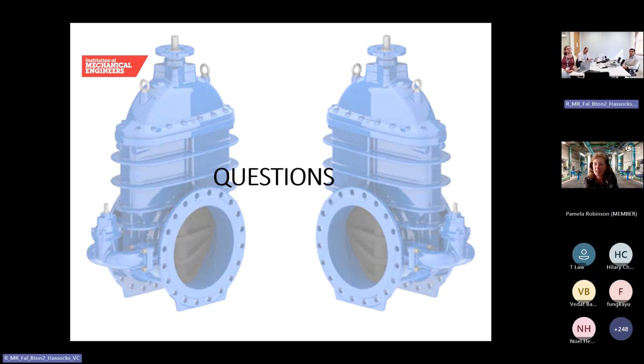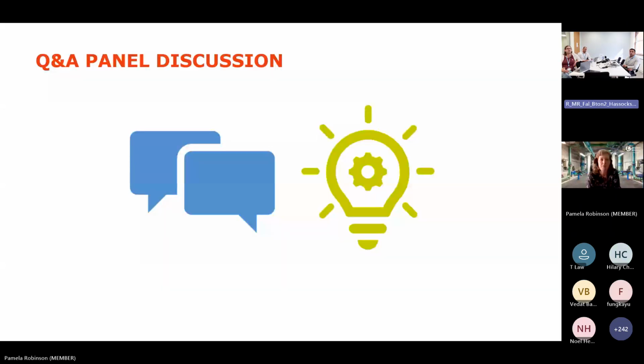So we use full bore and clear bore where, as was stated in the presentation, pipework is round, for example, but the throat of an eccentric plug valve can be rectangular. So if your pig is round, it's not going to go through a rectangular bore, even though the cross-sectional area is the same. Although it's not having an impact from a flow velocity perspective, you can't get a fairly stiff round pig through a rectangular hole. So that's why sometimes you have to specify clear bore, so that the throat of the valve is round and you can get a pig through it. Of course, if you're ice pigging, it doesn't matter, but with traditional pigging, where you've got big launchers and that in the pipework, that's why we say clear bore.